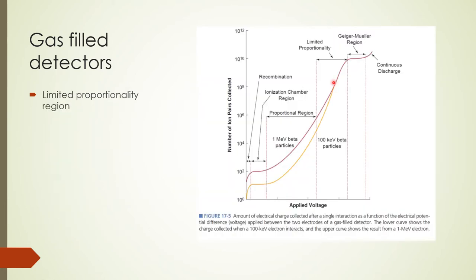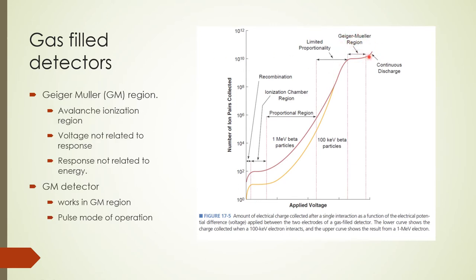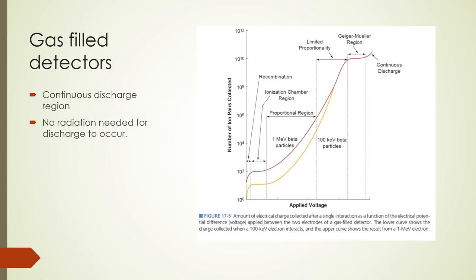Beyond the proportional region, we enter the region of limited proportionality as the voltage is increased further. The Geiger-Müller or GM region is beyond the region of limited proportionality. In this plateau region, there is an avalanche of ionization which represents almost complete ionization of the counting gas near the anode. Because of this effect, any increase in voltage does not increase the response, and the response is independent of the radiation producing it. GM counters are usually operated in pulse mode and are paralyzable unless measures are taken to avoid the effects. Beyond the GM plateau, atoms of counting gas near the anode may be ionized spontaneously, referred to as the region of spontaneous or continuous discharge, because the counting gas may be ionized even if there is no radiation entering the detector.